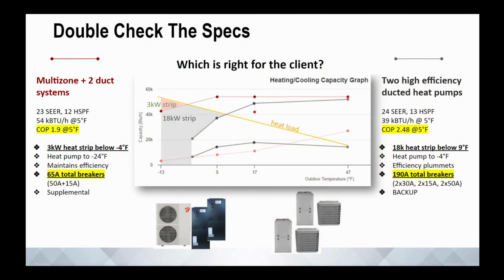So here's a different way to look at that. On the left side, down on the bottom, you can see sort of a picture, right? 1 outdoor unit, 2 air handlers. So it's a multi-zone. 1 outdoor, 2 indoors. Yes, this is doable. It sounds strange, but it's part of how these systems can work. On the right-hand side is 2 separate systems just duplicated. These are technically 3-ton systems.